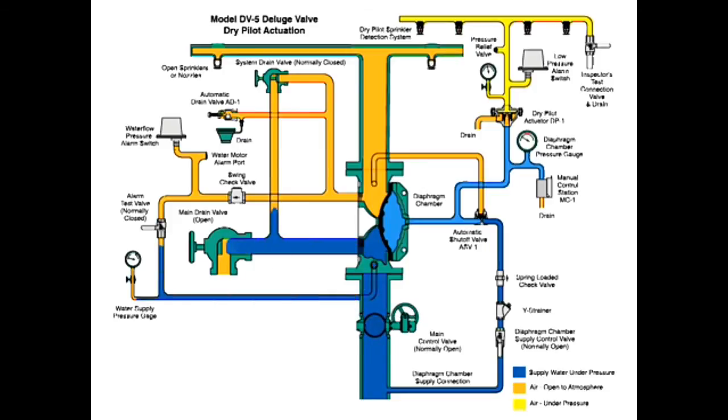Finally, slowly open the main supply valve and close the main drain once water begins to discharge from the drain. The system is then ready to return to service.